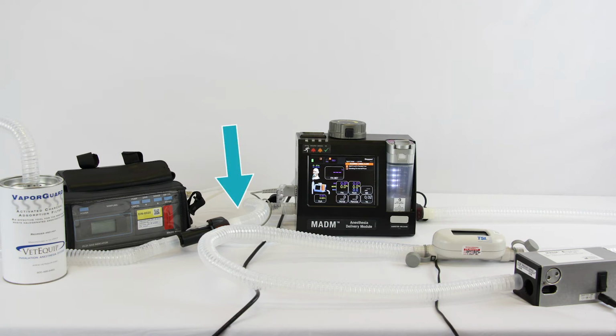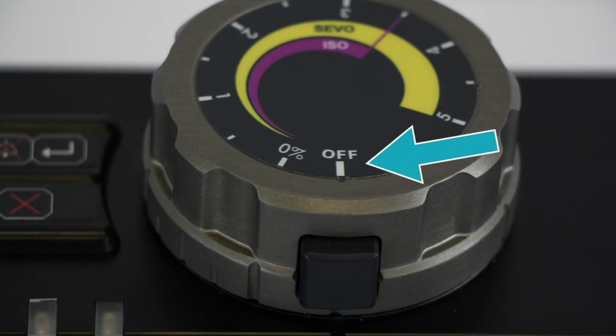Connect a third piece of patient tubing from the outlet port on the left side of MADM to a patient sensor circuit adapter connected to the patient anesthetic sensor airway adapter assembly. Then connect the external anesthetic gas analyzer to the open end of the patient anesthetic sensor airway adapter. Use the fourth piece of patient tubing to connect the external anesthetic gas analyzer to the charcoal absorbent filter. At the start of every operational test, ensure that the MADM dial is turned to the off position.